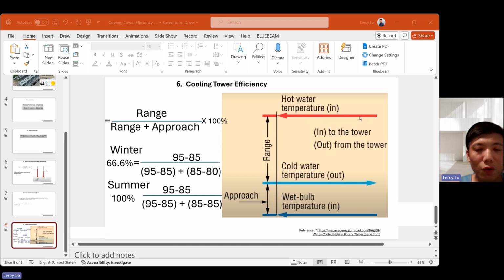Let's say 95 for your hot water temperature and 85 for your cold water temperature. Now your wet bulb temperature in winter, for example, is 80, and in summer is 85. So winter will be 66.6% for your cooling tower capacity, but in summer you will have 100% because you are losing that approach. You can see here, approach is equal to 0. So in this case, you might need another cooling equipment such as evaporative cooling for your summer worst case scenario to account for that.